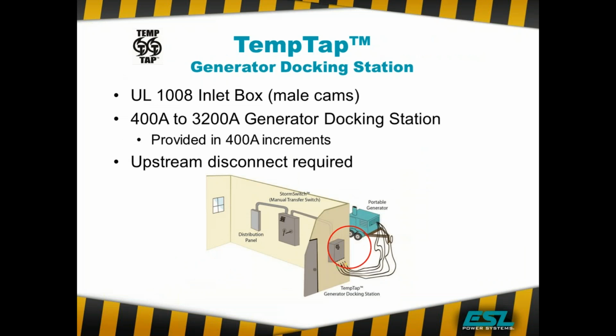Then the Temp Tap is a docking station where your switchgear, ATS, MTS already exists, and you're just looking for a means to provide a quick connect solution for the client. So a Temp Tap is used for generator docking stations. It has male cams signifying inlet power. They come in 400 amp increments. They're UL 1008 listed up to 3,200 amps. We've built them now up to 5,000 amps. Those above 3,200 amps are NRTL labeled.